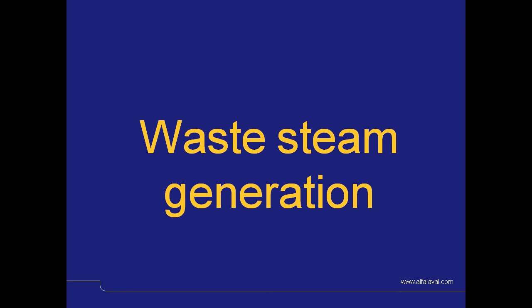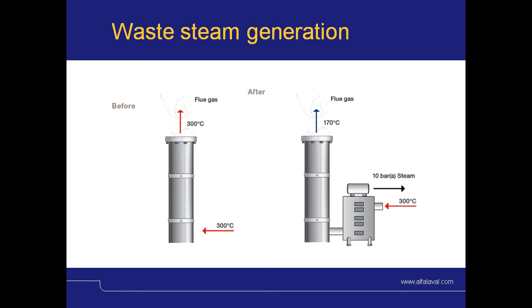Waste steam generation. Let's say we have a stream with hot flue gases, as the picture shows, that goes right out in the air. By installing a waste steam generator, it's quite possible to make use of a substantial amount of that heat. This steam can either be used directly in the plant or transformed into electricity. Here is the profitability calculation.